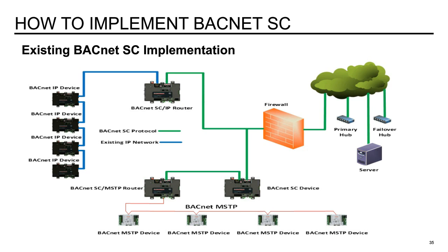Okay, thank you. And this question from David McDowell: does BACnet SC allow for automatic buffering of data to prevent data loss? Justin, you might want to weigh in on that. I know that with BACnet SC, the data is monitored to make sure the integrity is maintained, so you're able to detect if there's any data loss or data modification. But in terms of buffering, I'm not sure. I would have to research that and get back to you.